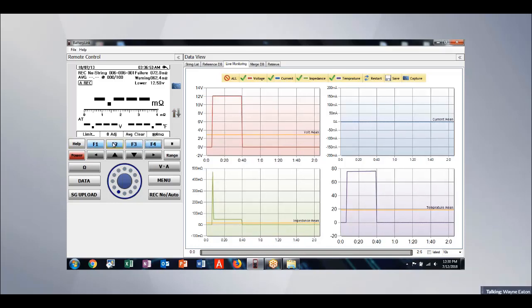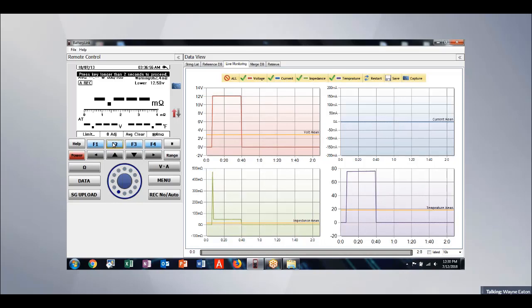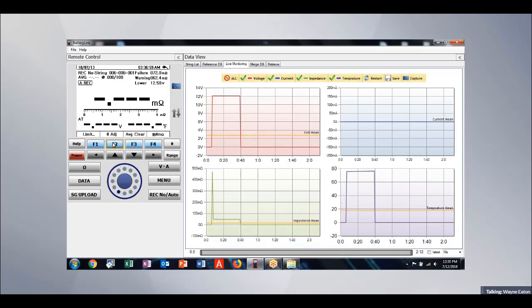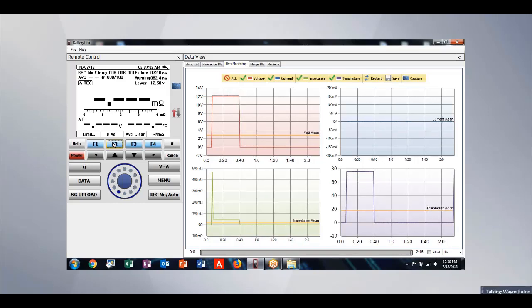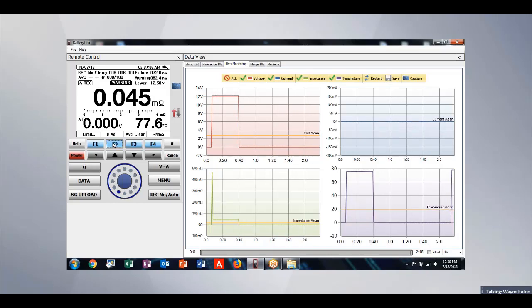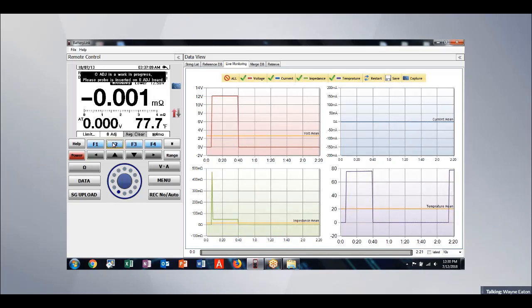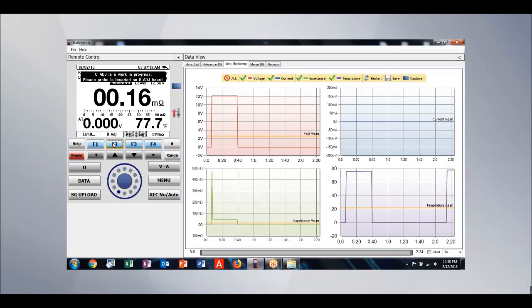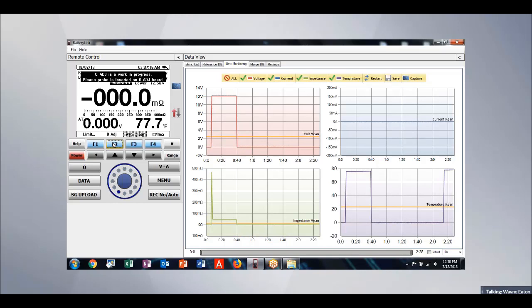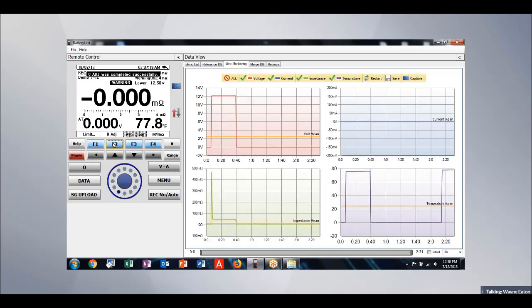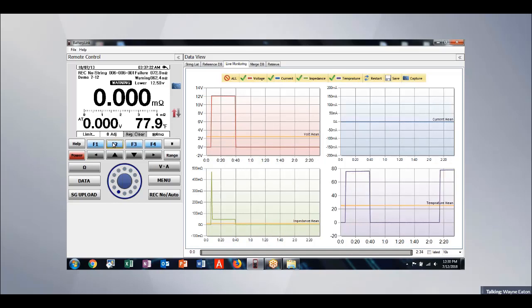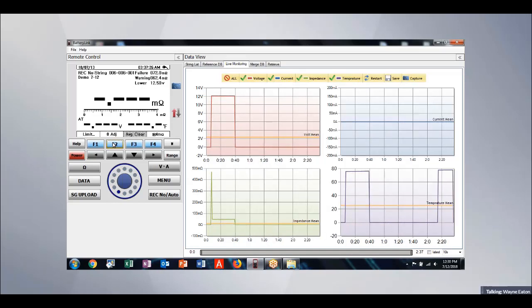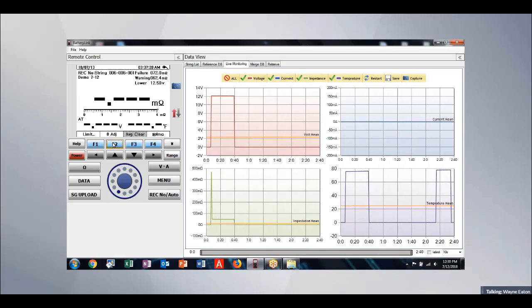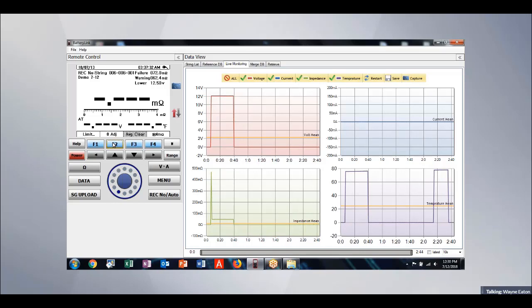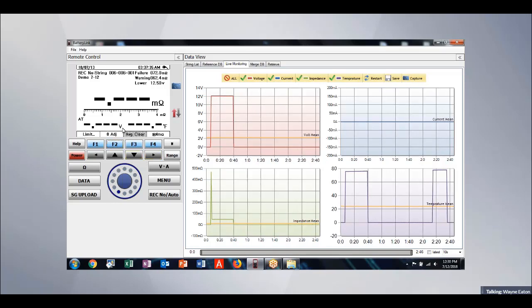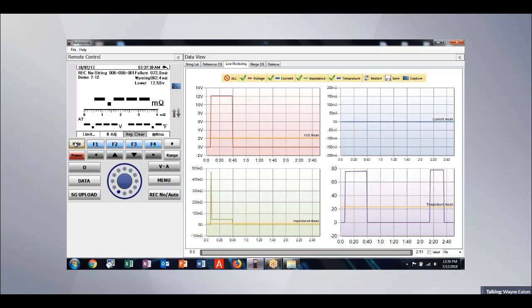We do have a built-in zero adjust. So if I change from the pin probes to a clamp probe, or I change out the probes themselves, I can do this zero adjust procedure. And what it does is it goes back through and it zeroes out the cable resistance for each of the ranges from the unit detection back out to the tips or clamps of the probes themselves. Like I said, the unit records the temperature at the negative post of the battery when it takes its measurements and records them.